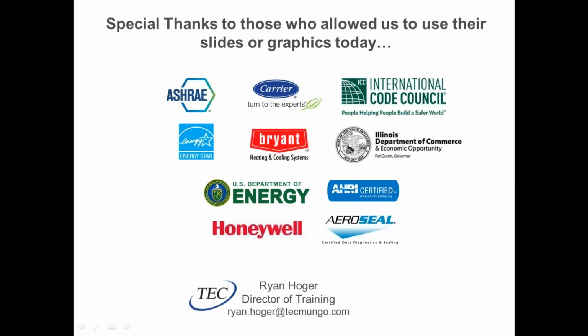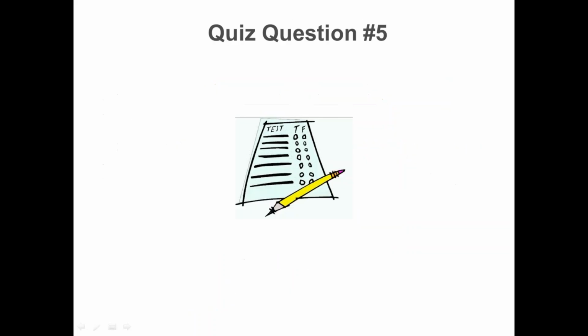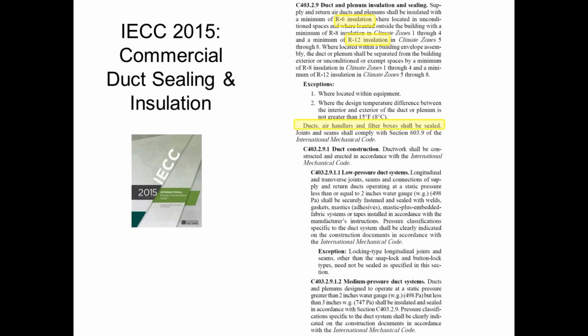Tom asks, do we need to insulate ducts in the plenum return ceilings? That's a great question, Tom, and that depends on whether your plenum return ceiling is considered unconditioned or not, and that's always been a debatable discussion. So, if you come up here, return duct plenums shall be insulated with a minimum of R6 where located in unconditioned spaces, right? So unconditioned spaces, most of the time your return plenum, if it's a return plenum, it is not unconditioned because the return ductwork is the ductwork. The ceiling plenum is the return ductwork. So that is conditioned by definition. So you would not need to insulate that for energy code purposes.